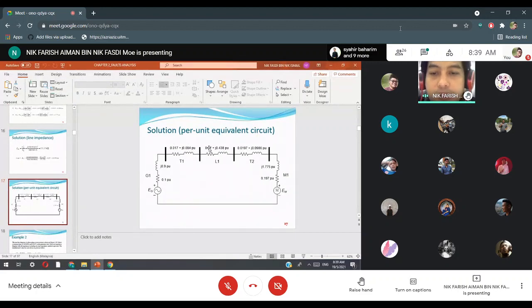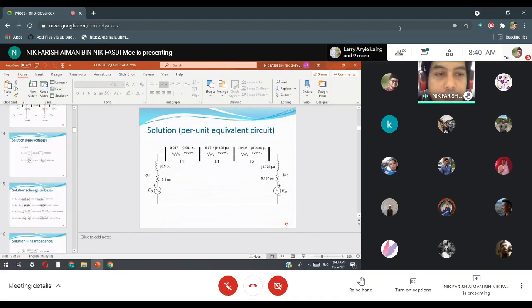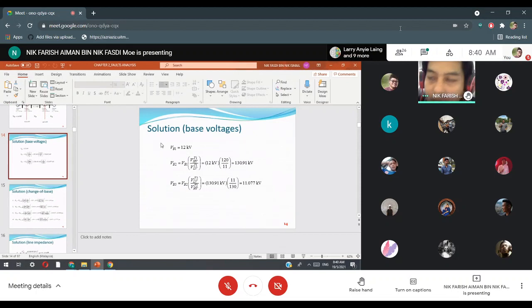So you need to know all the per unit impedance for each element - for example the generator, transformer 1, line 1, T1, T2, and load. So the first step, you need to determine the base voltage using this formula. Now we have all of VB1, VB2 and VB3.